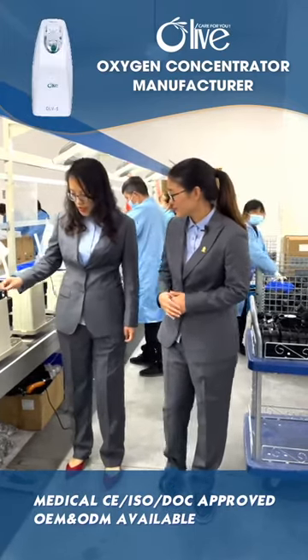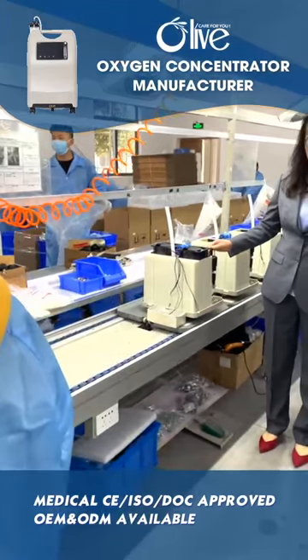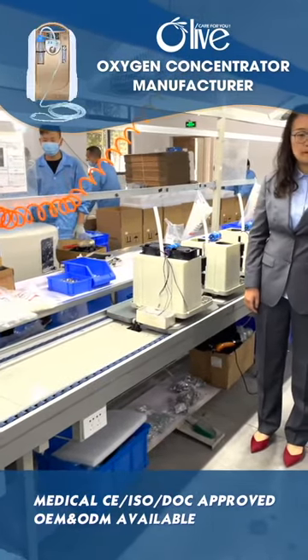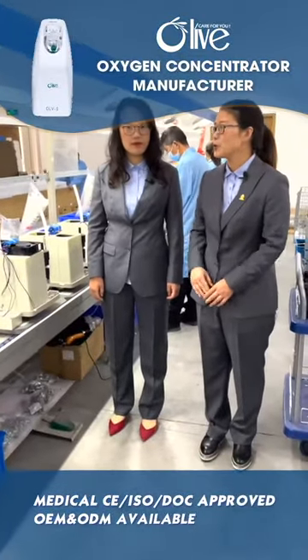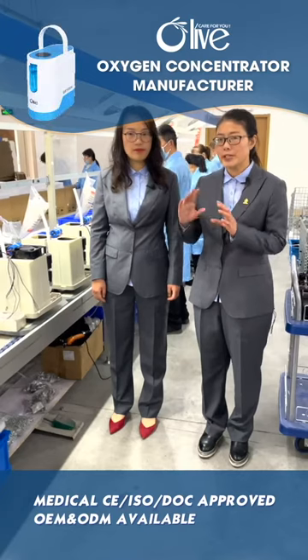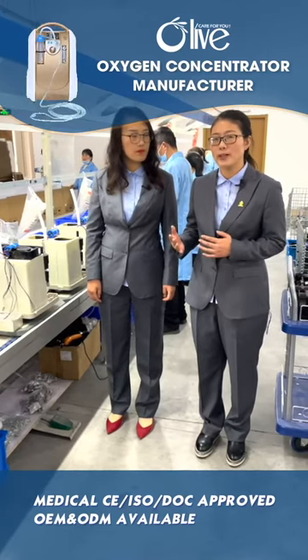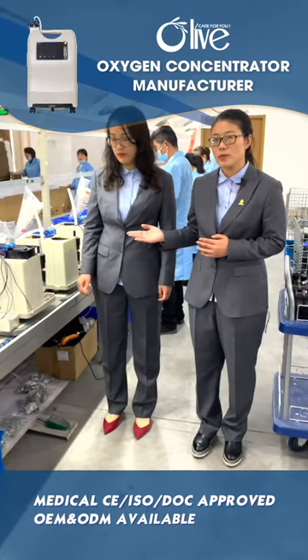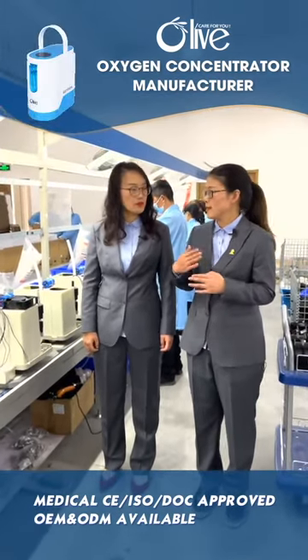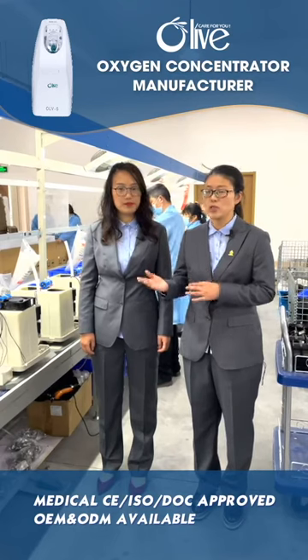I also checked there is a black part on the machine. What's this for? This black one? We call it a silencer. You know the air compressor cover just now is used to reduce the sound caused by the air compressor. And this one, the silencer, is also used to reduce the noise coming out from the oxygen concentrator.